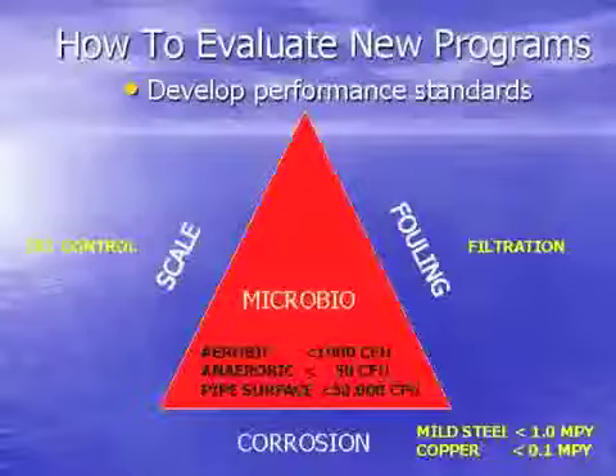If you're using ozone, you have to be careful, because how are you going to control the scale on that side? If you fed a phosphonate, which we talked about earlier for scale control, the problem is ozone chews that up too - anything in its path, it basically goes after. So we don't see ozone anymore as a standalone program; we see it used in sporadic cases, or maybe not at all, because of the cost it takes.